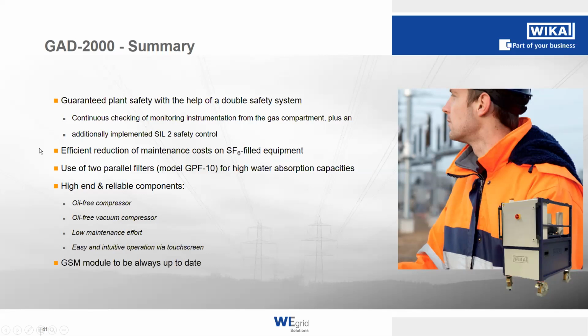We definitely have the advantage that we don't have to put the GIS out of service to do all the maintenance for the lowering of the humidity. We have two parallel filters, so we can absorb a lot of humidity. And of course, with all our units, we have high-end and very reliable components like the compressors and the vacuum pump, and also we have the HMI control as well as the GSM module for remote connection if necessary.